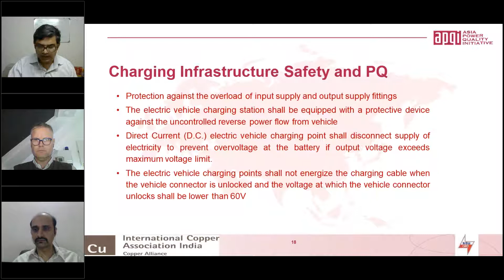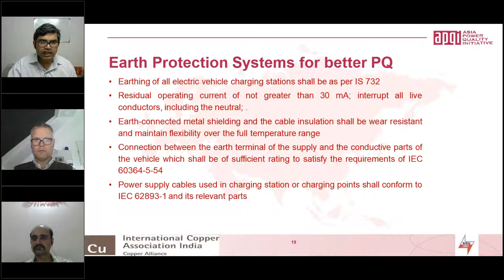Earth protection systems for better power quality. Earthing of all electric vehicle charging stations shall be as per IS code 732. It is the code for the wiring installations. Residual operating current of not greater than 30 milliampere. This is the limit, and interrupt all the conductors, including the neutral, if this limit is exceeded. Earth connected metal shielding and cable insulation shall be wear resistant and maintain flexibility over the full temperature range. Connection between the earth terminal of the supply and the conductive parts of the vehicle shall be of sufficient rating to satisfy the conditions of IEC 60364. Similarly, another IS has been mentioned with which the power supply cable should comply.